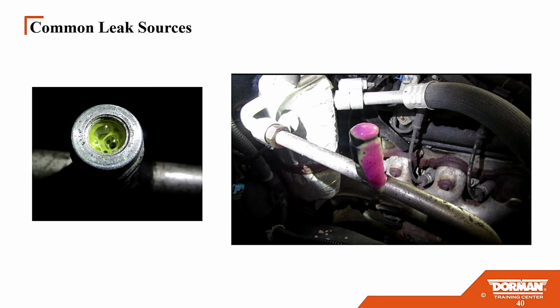And of course, common leak sources right there. Your cap, your primary seal, is a cap, you've got the little rubber in there, but don't forget, how good is it sealed? Even the Schrader valves, believe it or not, you got to be careful. There is such a thing as under-tightening and over-tightening.